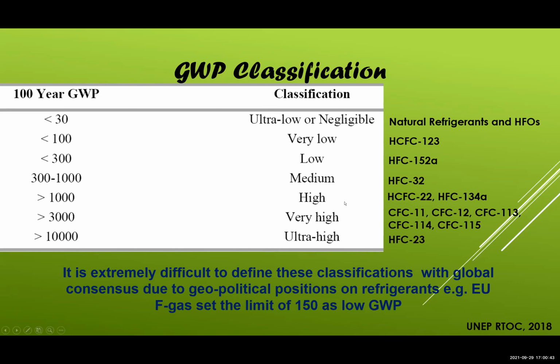So most of the current HFCs will fall under high, except for R32. R32 GWP is 675, so it will fall under medium. HFC 152A is low because it is about 100 plus, and R123 is low. But most of the HFOs and natural refrigerants, we call ammonia or hydrocarbon or CO2, they will all fall under ultra low or negligible, less than 10.